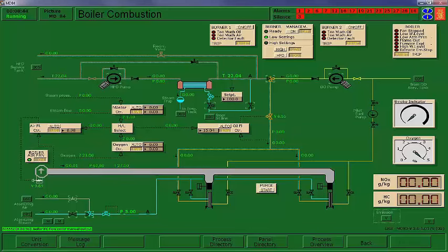Now, any boiler that you go to, you're going to have to play with the settings. But about 15% firing rate for startup is a pretty good average. And what we're trying to do is raise the firing rate up a little bit so that initially we hope that flame will establish. If we try to start out very, very minimalistic, there's a good chance it wouldn't light.